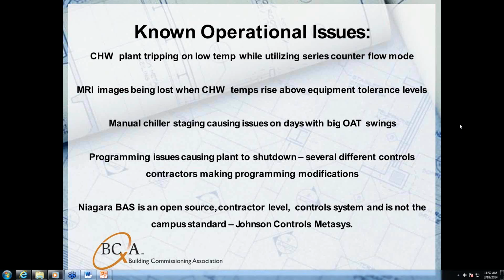They also had manual chiller staging as part of the plant programming. So on days when there would be big outside air temperature swings, they would experience issues. They have a small facility staff. They're not able to sit there and babysit the front end all day. So they would do one of two things. They would false load the chiller, because we did discover that this plant was fairly oversized for part load operation. So they would false load the plant in order to keep it running when they knew the outside air temp was going to rise that day. Or they would go about their daily maintenance tasks and wait for pages that they had set up. So they'd have a pager, they'd get an alarm, and they'd have about 15 minutes to get back to the plant and get a chiller up and running before that MRI loop would rise above its tolerance levels. So both are bad.